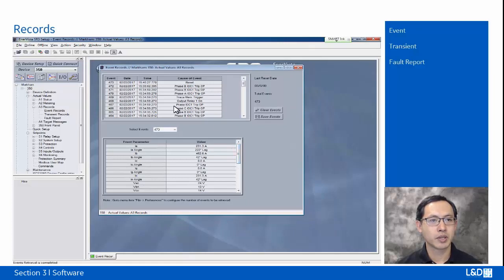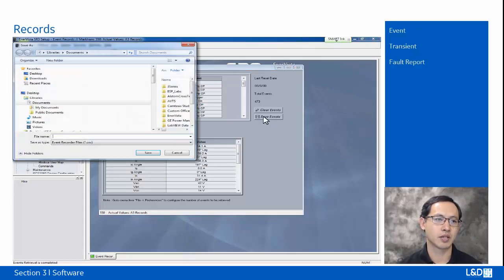In these records, we can see the event numbers. We can have a pull-down list to select the events. When you select the events, all these events will be displayed. For example, 466 is a phase C IOC trip operation, and you can see the parameters, current and voltage, phase angle, etc. displayed. You can save these events, or you can clear these events. So for example, if you save, you will save as a CSV file.